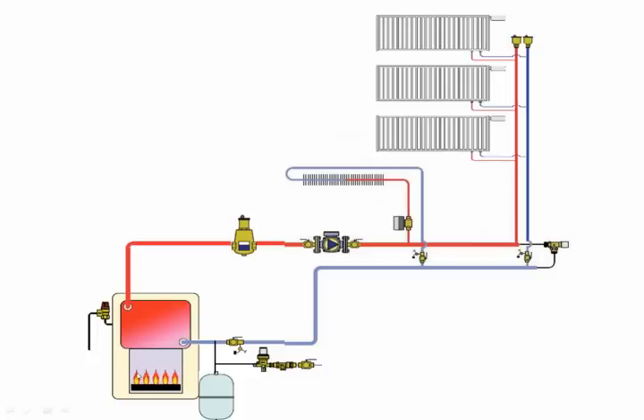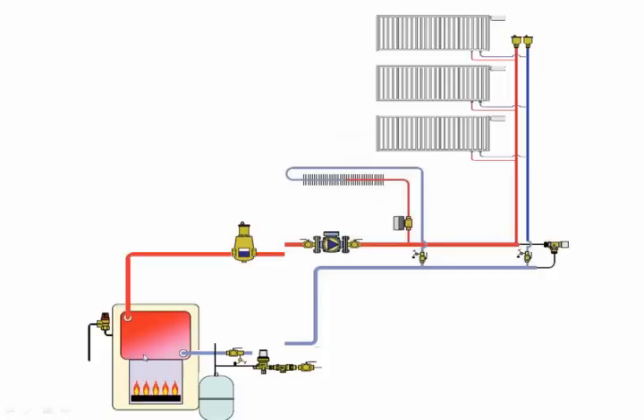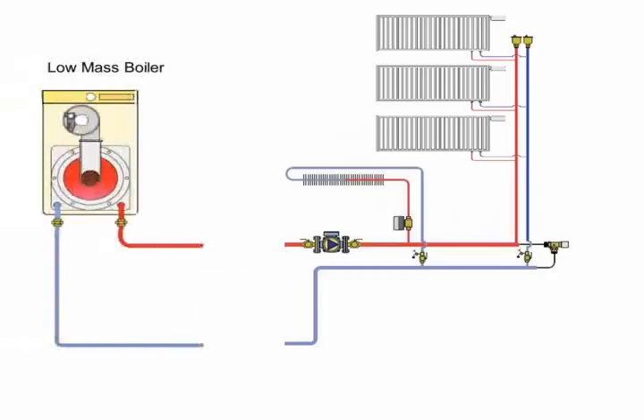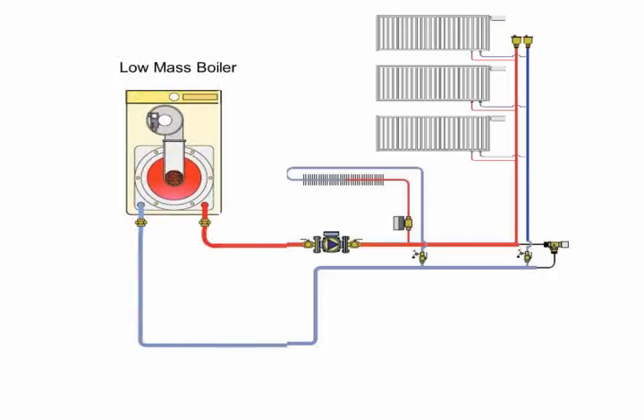Okay, let's go back to our system here, and let's take a look at our boiler. We're going to start talking about some other items. Let's say this boiler wears out in time, and you, the engineer or designer, want to replace it with more modern equipment, say a condensing boiler. Many condensing boilers have heat exchangers that don't contain much water, low mass, okay? Now, where would you put your air separator to be most effective?